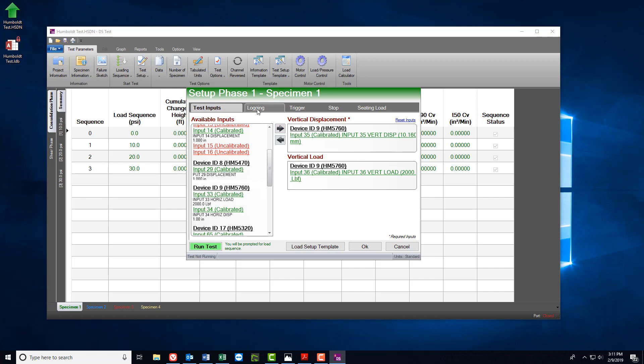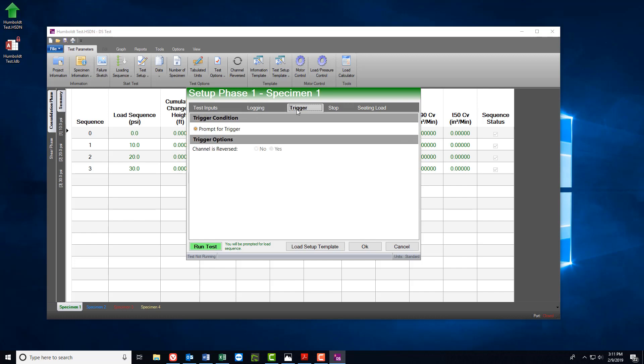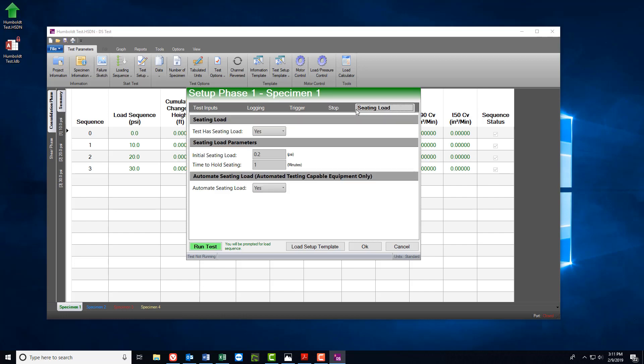From there, move through each of the tabs, including Logging, Trigger, Stop, and Seating Load in order to ensure that the test parameters that you wish to use are set. Once you're satisfied with the appropriate parameters, go ahead and select OK.